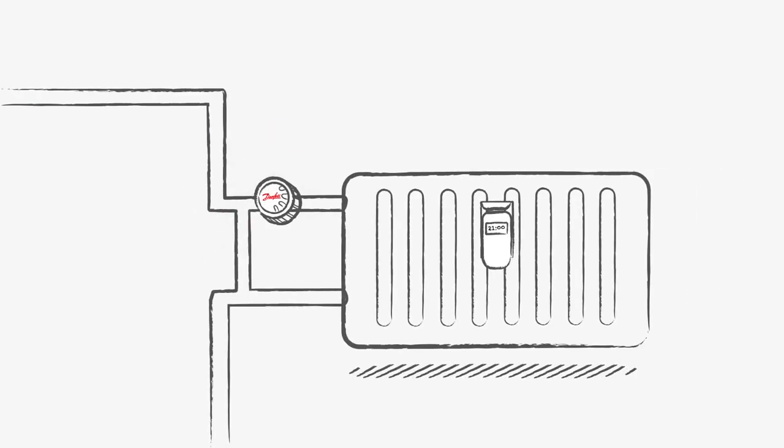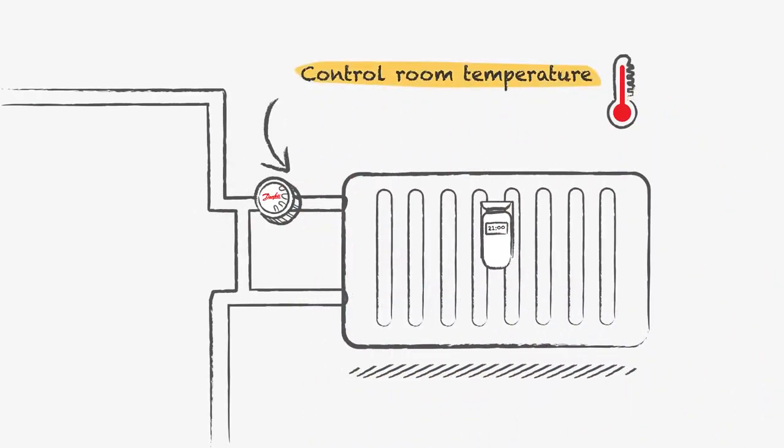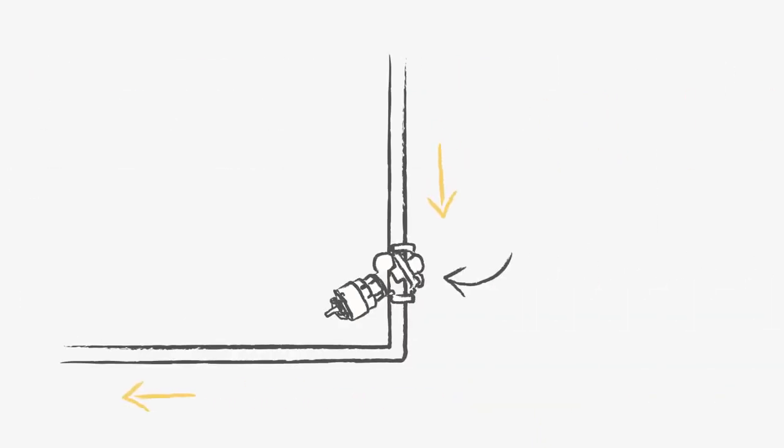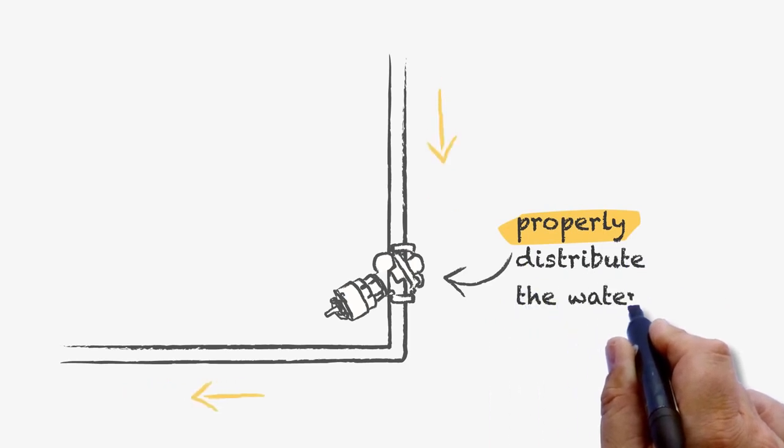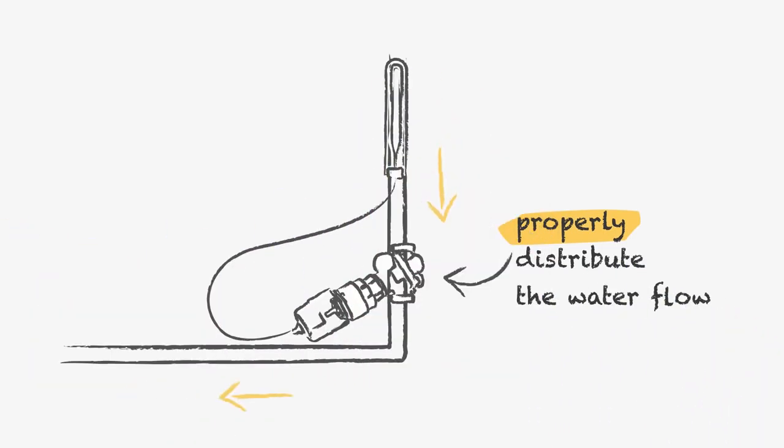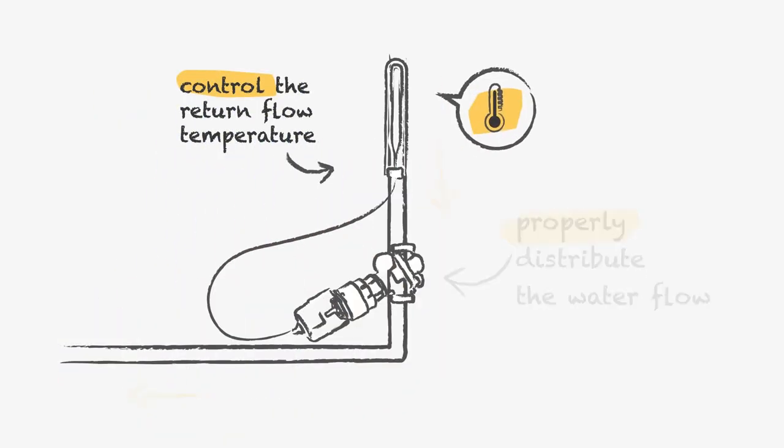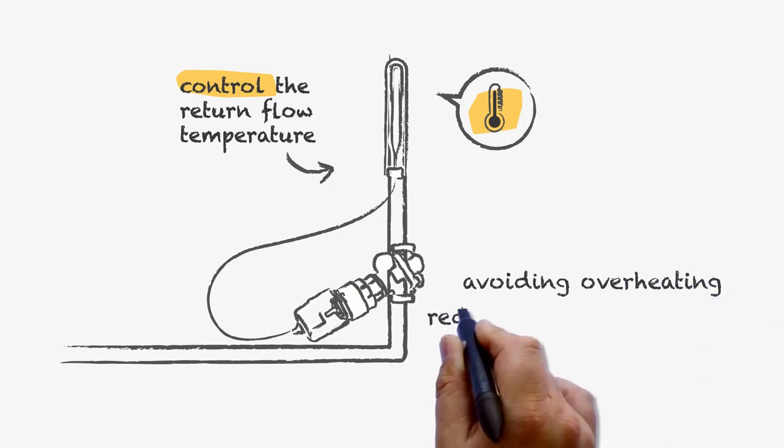The thermostatic radiator valve is there for the resident to control the room temperature. The ABQM pressure-independent balancing valve will properly distribute the water flow through the installation, and the actuator with thermostatic element will control the return flow temperature in the riser, avoiding overheating and reducing unnecessary flows.